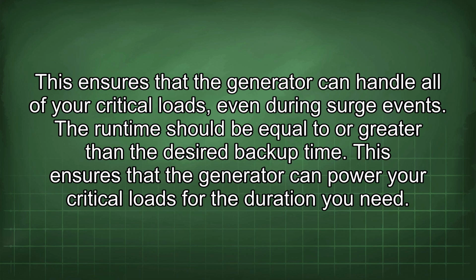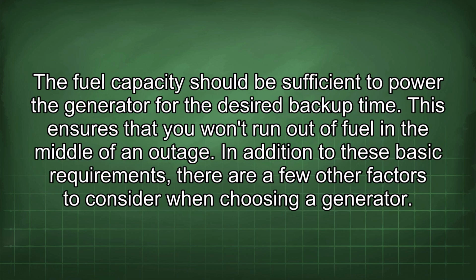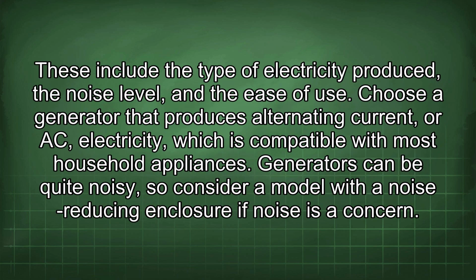The runtime should be equal to or greater than the desired backup time. This ensures that the generator can power your critical loads for the duration you need. The fuel capacity should be sufficient to power the generator for the desired backup time. This ensures that you won't run out of fuel in the middle of an outage. In addition to these basic requirements, there are a few other factors to consider when choosing a generator. These include the type of electricity produced, the noise level, and the ease of use. Choose a generator that produces alternating current, or AC, electricity, which is compatible with most household appliances.